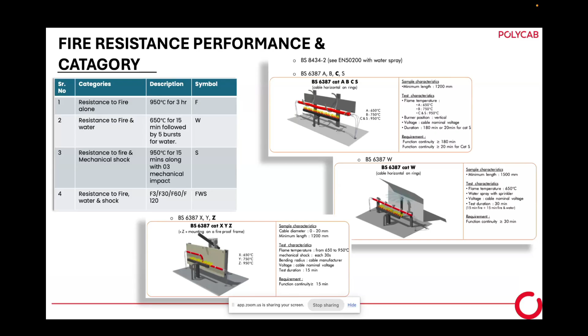In BS category, if you want to designate a cable, you can say FWS, or in BS 6387 terms, CWZ. CWZ is very widely popular, and many people know that when they place an order for a CWZ category cable, it means it can withstand fire intermittently, withstand water intermittently, and also withstand mechanical shock.